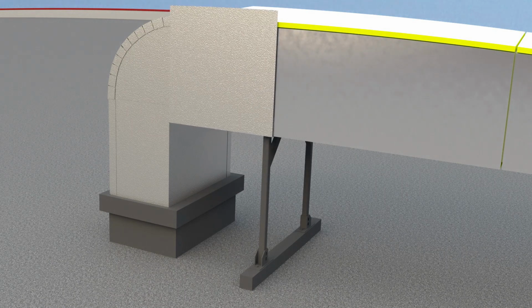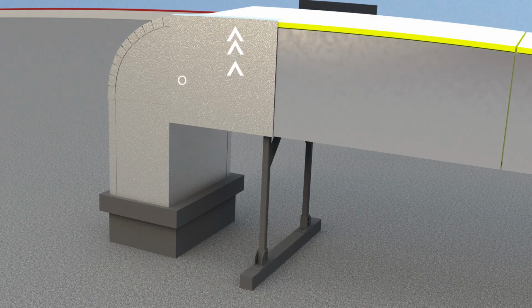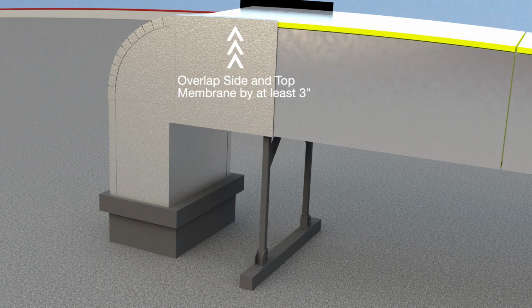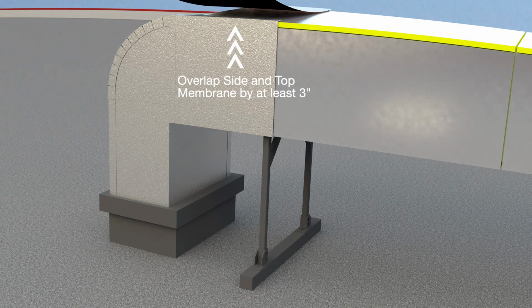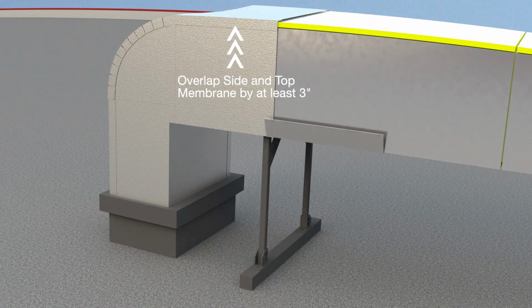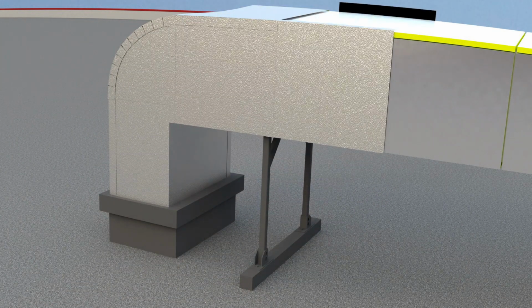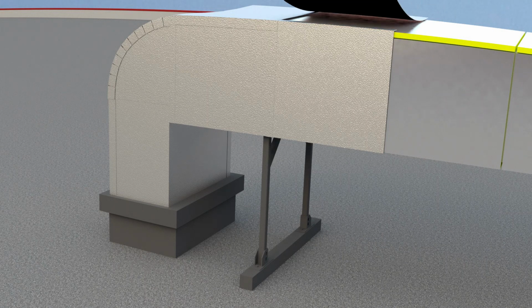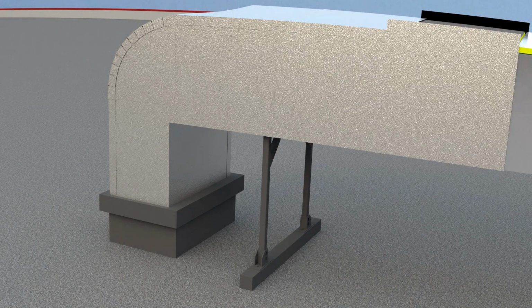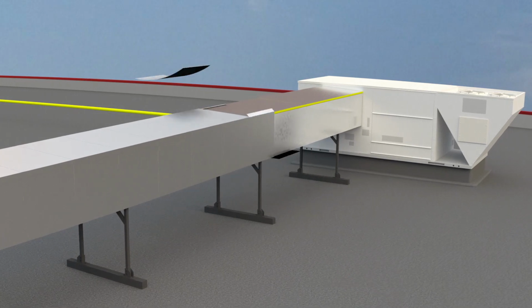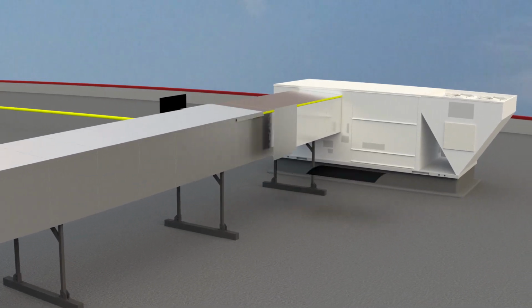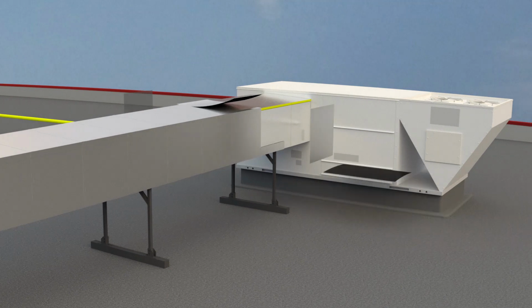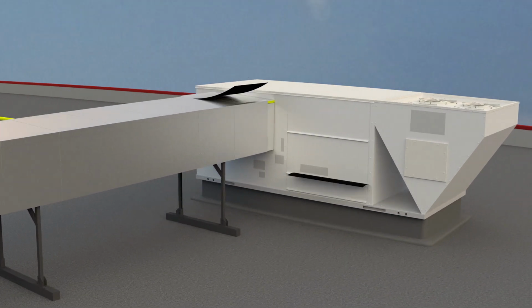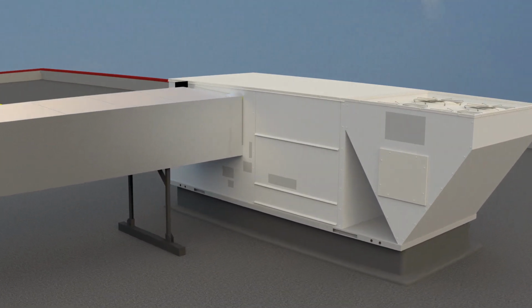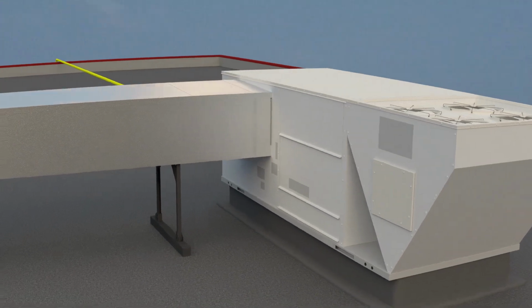Side pieces start flush with the bottom of the insulation and overlap 3 inches onto the top surface. And finally, the top piece of FlexClad must also overlap 3 inches onto each side. Continue this process for the balance of the ductwork. It will be necessary to cut the membrane at the support pedestals. These cuts can be sealed with an MFM-approved sealant to avoid water penetration. Always roll the membrane into place as you move from section to section, paying special attention to all overlaps.